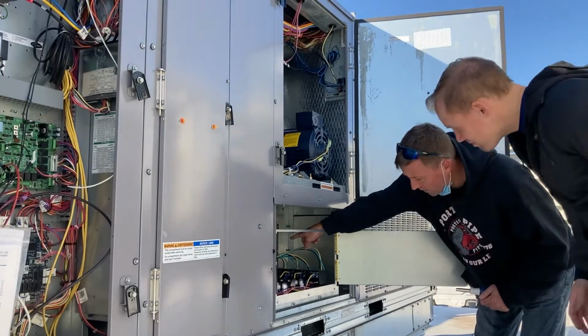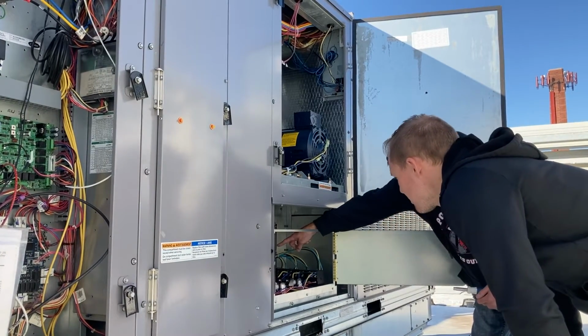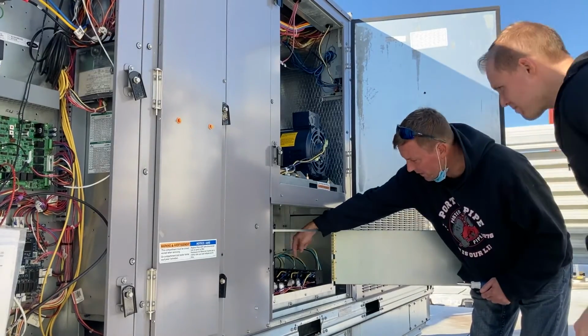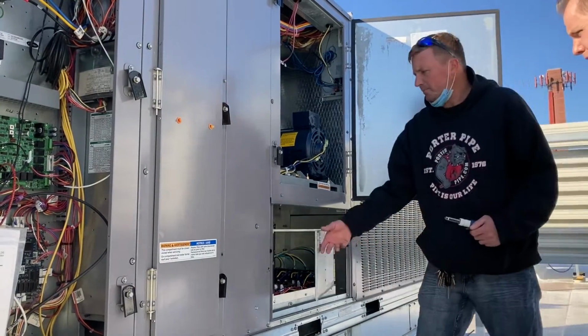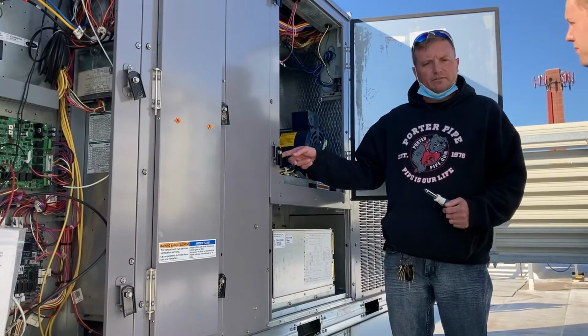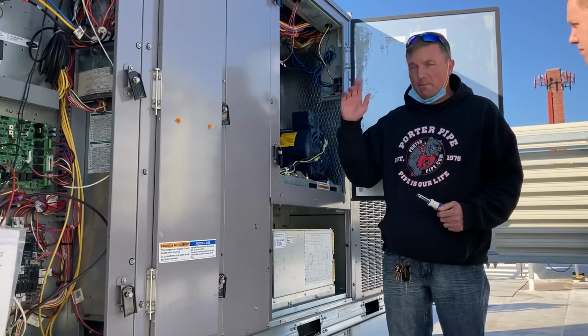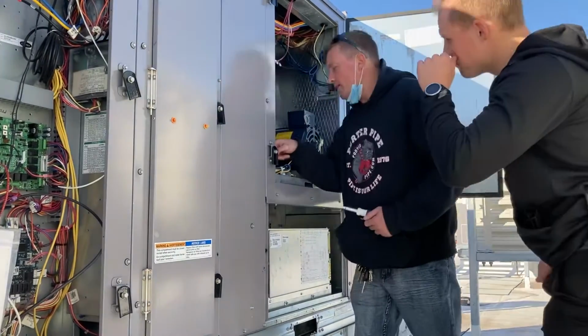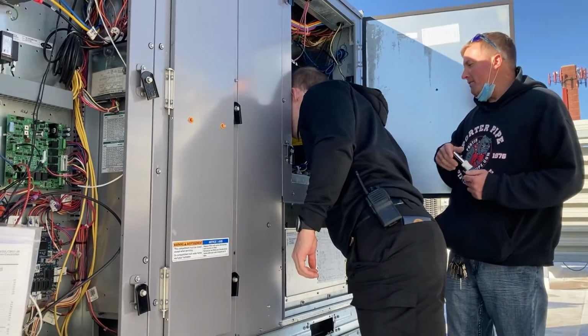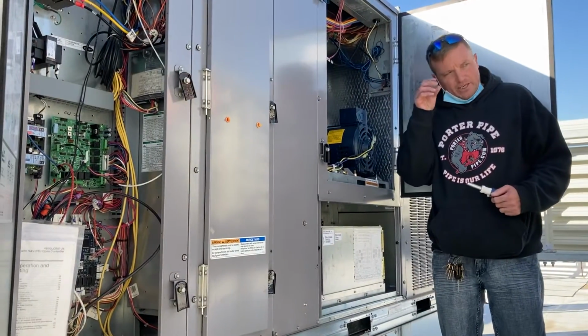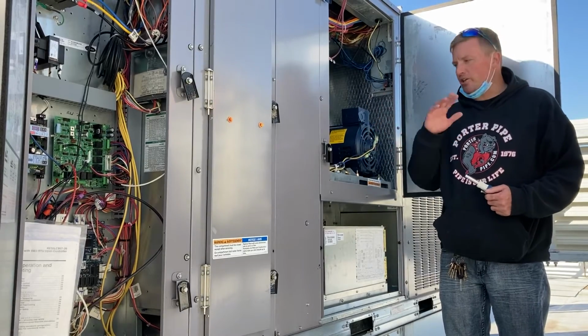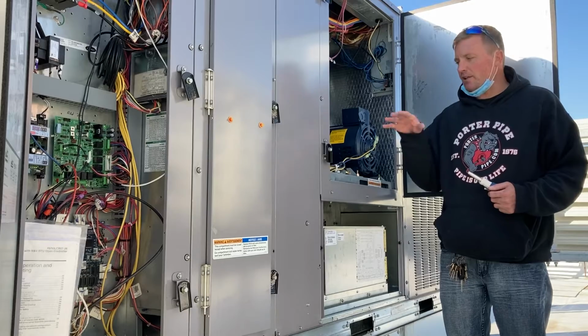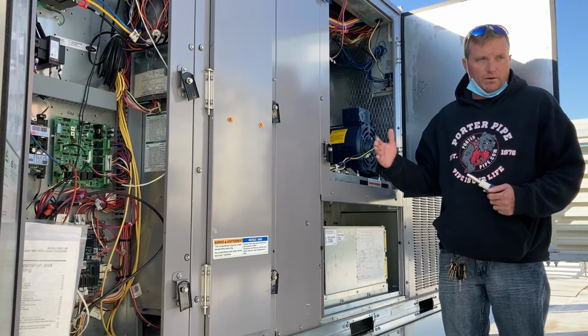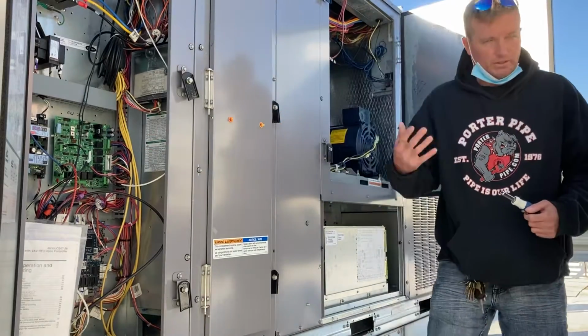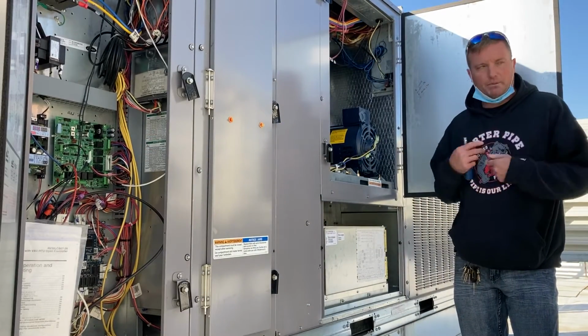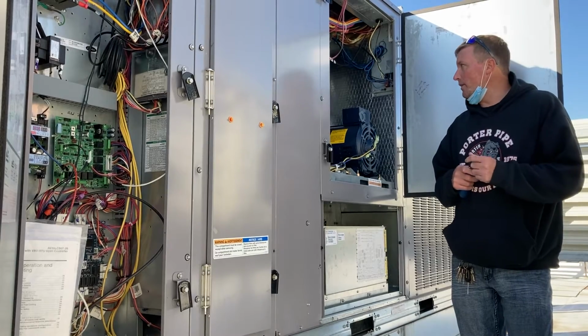That right here is our limit. So if anything trips there, it'll trip the SCR relays, which bring in the contactors. Okay. Current sensing relay: if the fan's not running, nothing's going to run. So if you come up here and the fan's running, if you look on this, a red light means on. If it's not running, use a mini screwdriver and try to get it adjusted. If you can't get it to adjust, unfortunately the automation would have to override the alarm, or I would have to come out, log into the computer, and override the alarm. So there's really nothing I can personally do with that, okay? So at the end of the day, that's what that is.